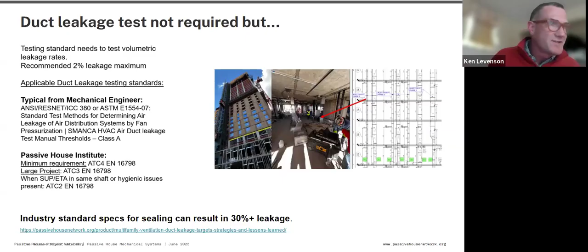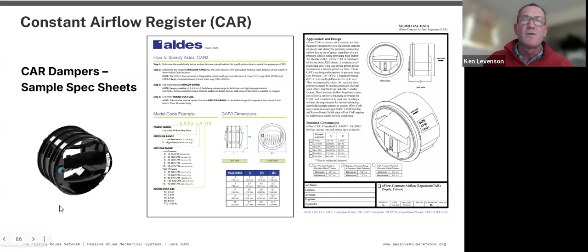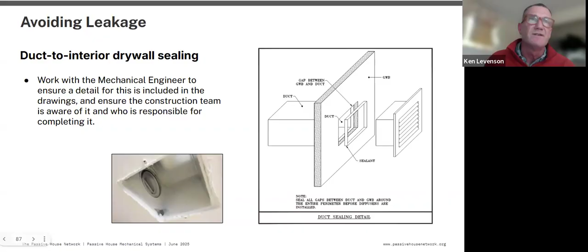The other aspect is it can be much tougher to balance the systems and maintain airflows. So things like a constant airflow register are quite typically used, where we have ducts and it's coming into contact with the interior construction here, and you have these parts and pieces where the air could actually be leaking back into the construction and not getting to the space. There becomes a requirement of quite good care and practice to make sure that those are all sealed as well.